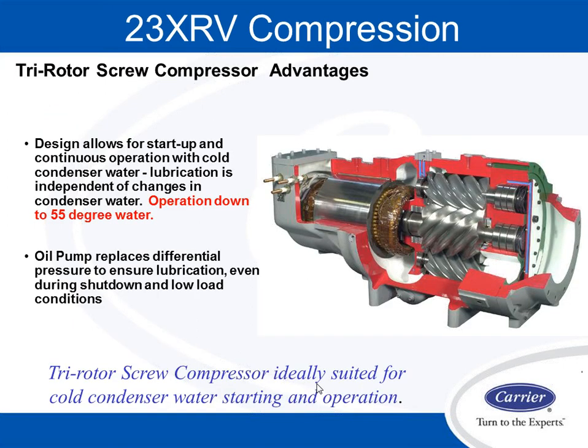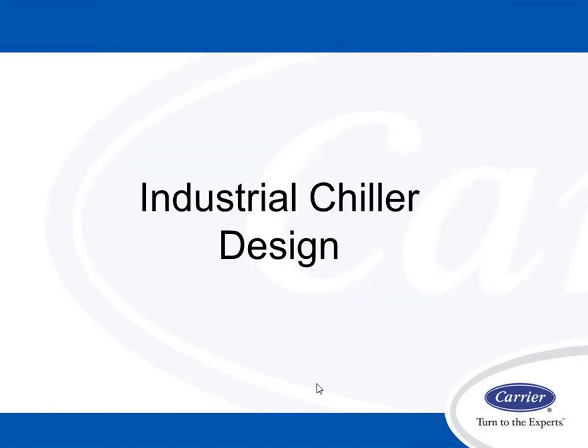Okay, here's the cutaway of the machine itself, and if you have a chance to look at this machine operating, look at the compressor in the cutaway. It is an absolute tank of a compressor. We have 3 moving parts, the 3 rotors. The good thing about the screw: most screws can only operate down to 70-degree entering condenser water, because of the oil lubrication system. This has its own independent oil lubrication system, and we're able to operate with condenser water temperatures down to 55 degrees. So that is really, really important.